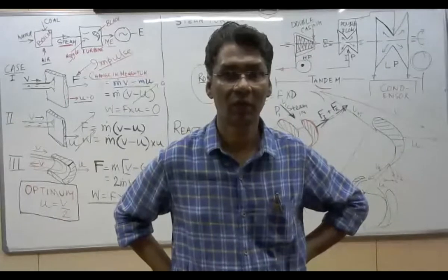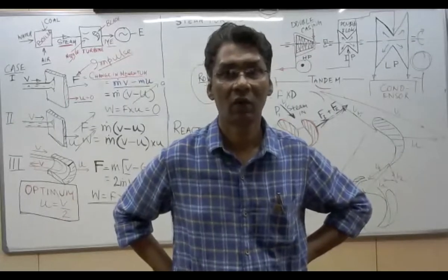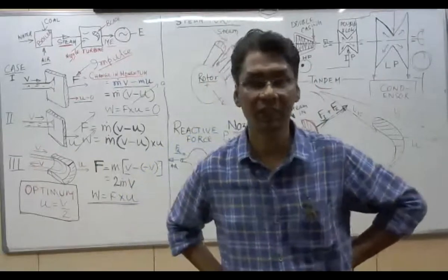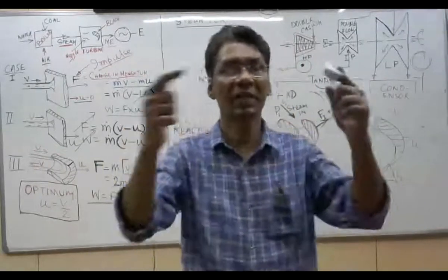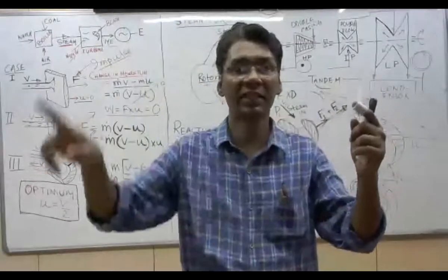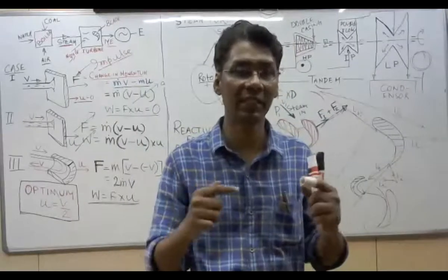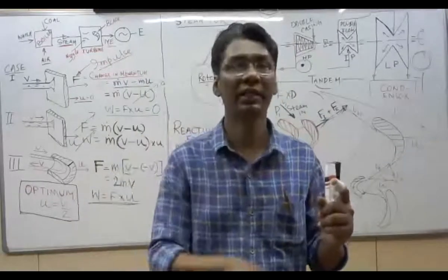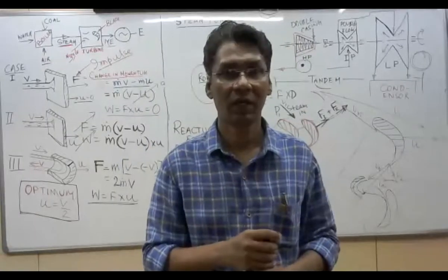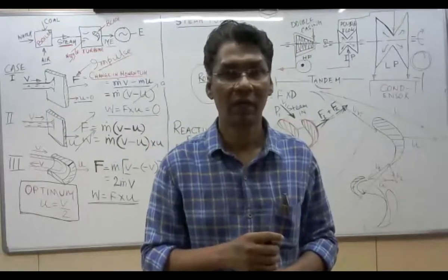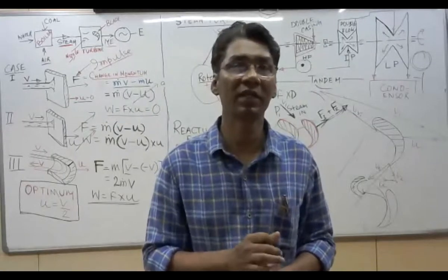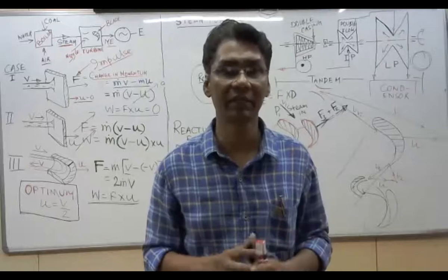Why are holes present in the blades? Holes are present in the blades to connect the blades together for increasing stability of the blade at high speed. That is called lacing wire to be placed. Lacing wire is placed into the hole and it is connected together. Labyrinth. Labyrinth is nothing but sealing of the steam. Gland sealing is called labyrinth.